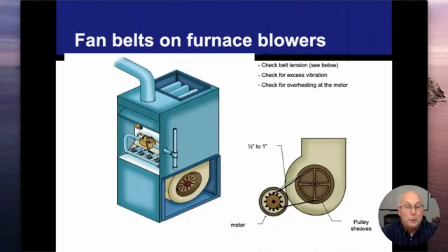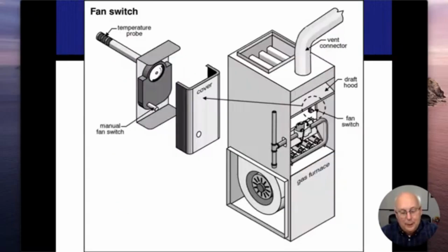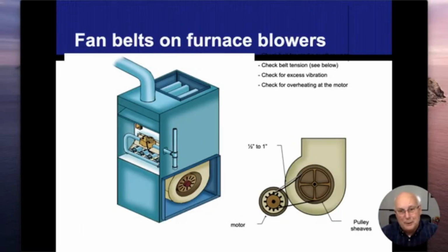Older blower fans, belt-driven ones, I would encourage my client to get a belt and leave it on the ground there. Those things break at the worst times. But again, if I start seeing these older things nowadays, I would have to warn my client that this is just an older unit and it will fail eventually, and they're going to be getting an upgrade as that comes along. Everything now, these blower fans, they're all direct drive, so the motors are actually built into the fan, so we don't use belts anymore. And they're also multi-speed ones, or adjustable speeds. So you can actually program them on the computer by how much air it forces through the ductwork. And as I said earlier, cold air, harder to push, more fan speed. These belt-driven ones, they were one speed only.